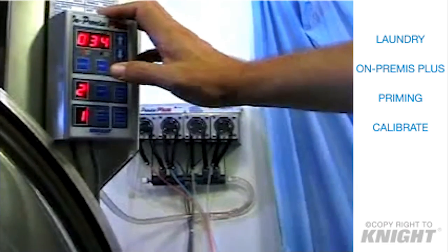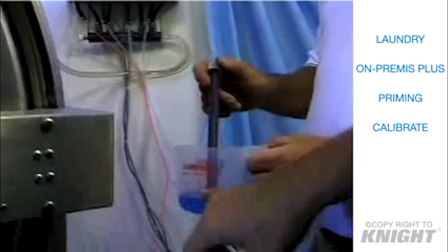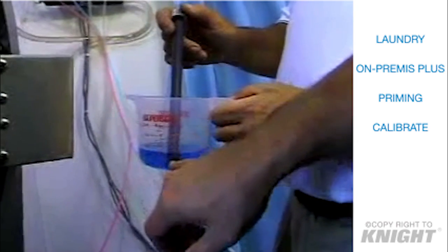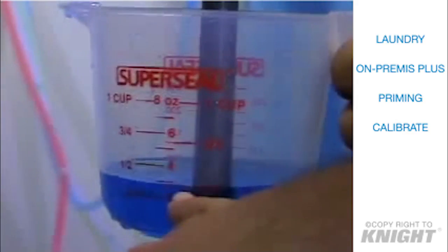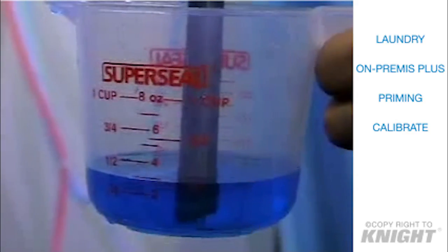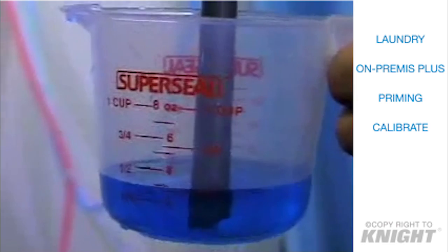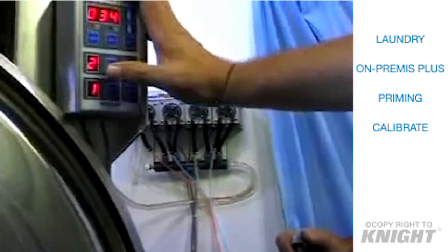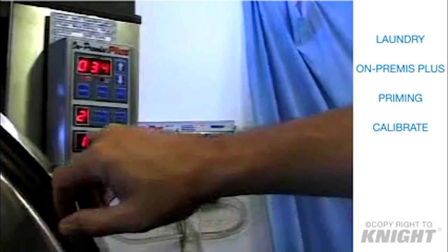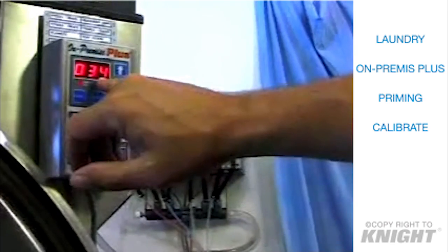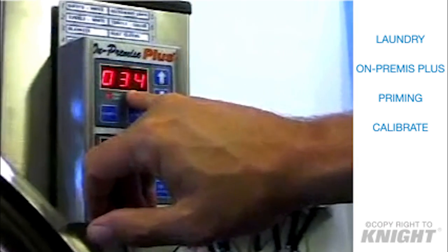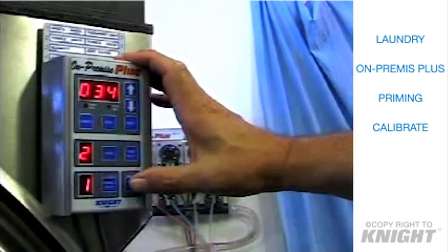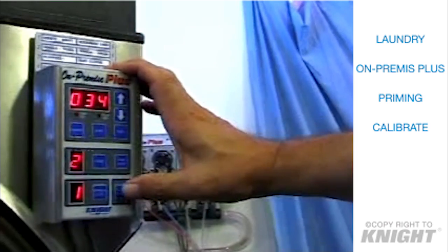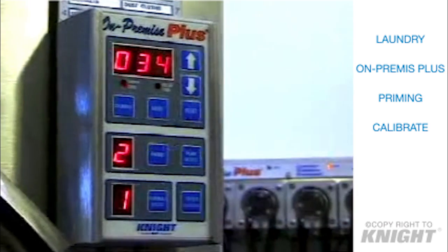We've stopped the pump. Now we're going to measure where we started, which was up here at 8 ounces. We drew off right close to the 3 ounce mark. So we're going to call that 5 ounces. But that time's already recorded by the pump. And so for formula number 1, when pump 2 is triggered, that's the time that it's going to run, 34 seconds. And press enter to accept that calibration timing. That's how you use the other mode of calibrating.